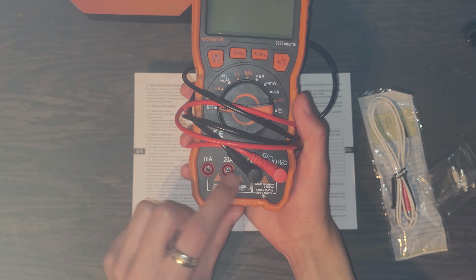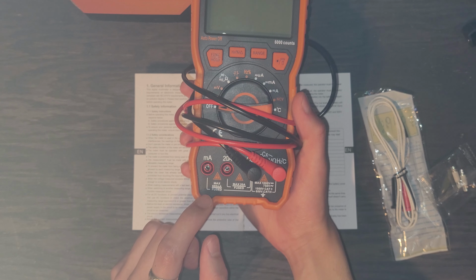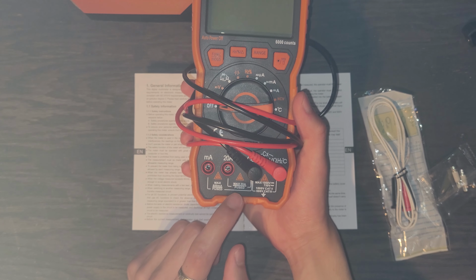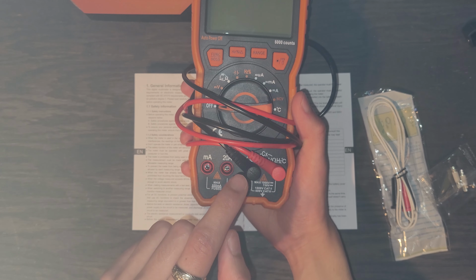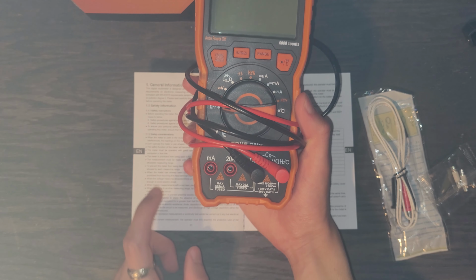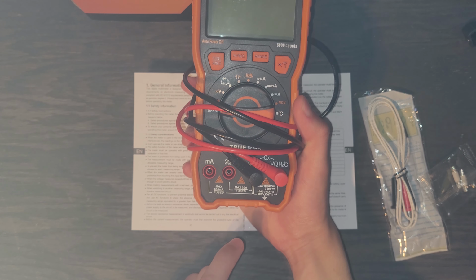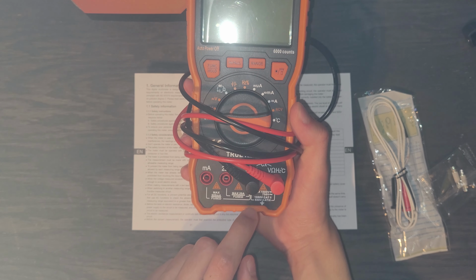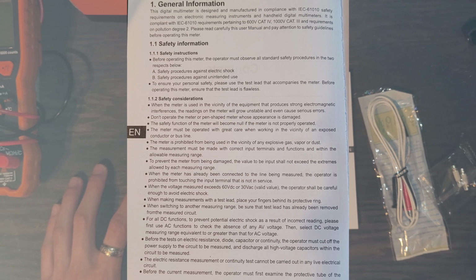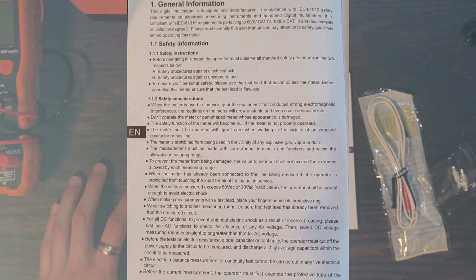So if we use these two ports, we would have a max of 600 milliamps fuse, max of 20 amps. And the 20 amps is going to this part and this part. And then we have a max voltage as well here. And then we also have our grounding, so that's important to look at. When the meter has already been connected to the line being measured, the operator is prohibited from touching the input terminal that is not in service. When the voltage measure exceeds 60 VDC or 30 VAC, which is the valid value, the operator shall be careful enough to avoid electric shock, so that's on you.